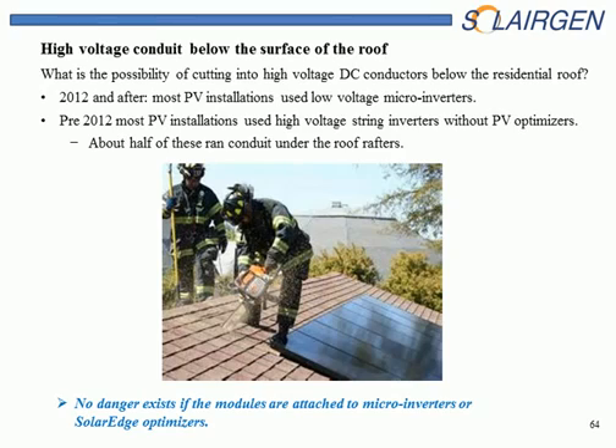High voltage conduit below the surface of the roof. So what's the likelihood that you'd run into that? 2012 after, probably very unlikely, because microinverters were used and then PV optimizers with the SolarEdge were used. Pre-2012, it's a possibility that there's a high voltage string running below the surface. If you don't see that conduit running off the side of the roof, then it runs below. And most of the time it drops straight down to the ceiling joist. Occasionally they'll run horizontally along the rafters.